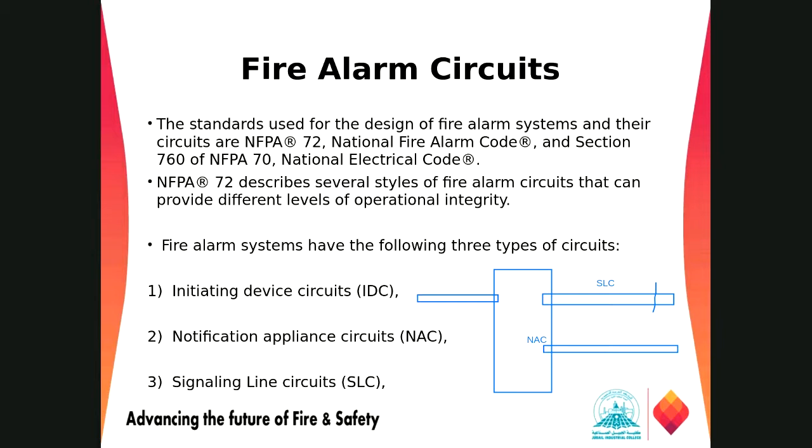So those alarm devices are connected in this NAC circuit. Let's say this is a horn, a strobe, and all kinds of communication systems, the public voice communication system. So it will give us an alarm, and the occupants will just leave the building. One circuit for smoke detectors, another one for strobe and horn, right? Yeah, exactly. Okay. Now in the same system we also have the IDC.